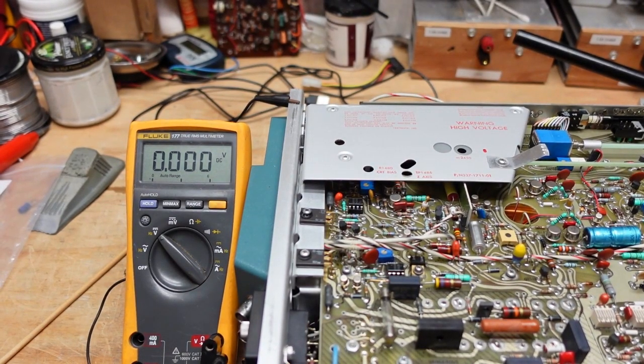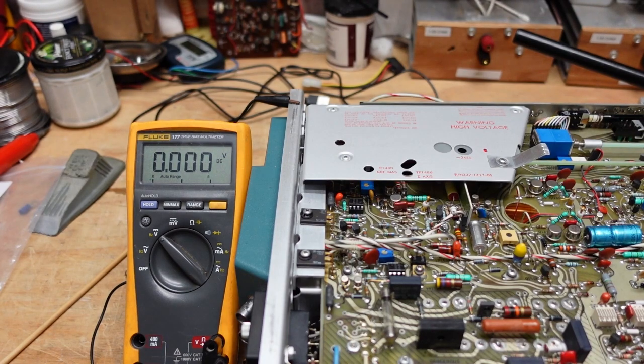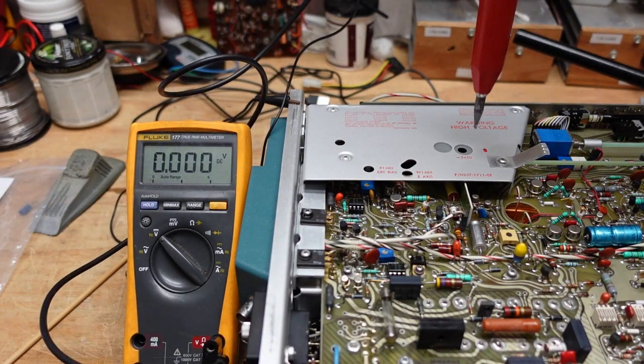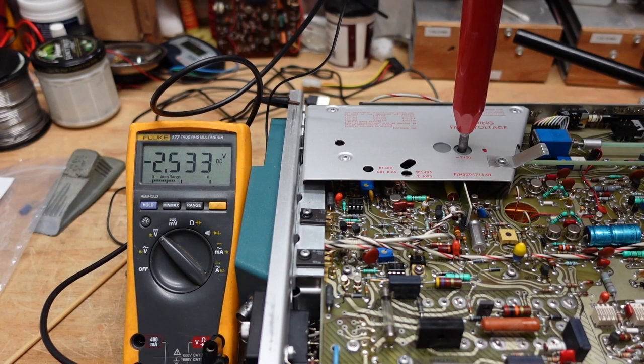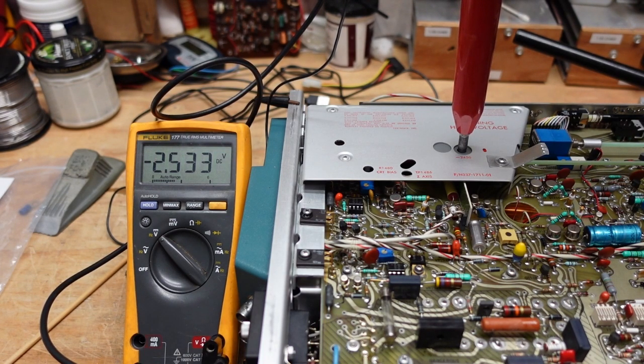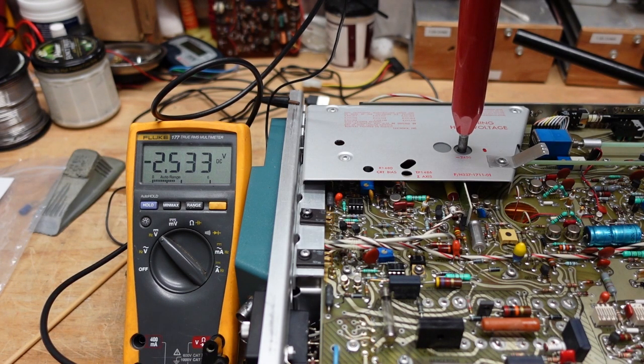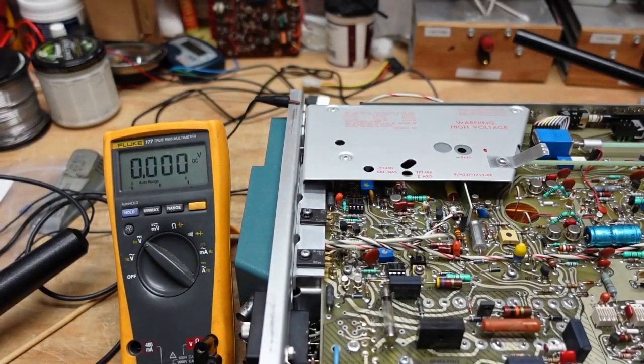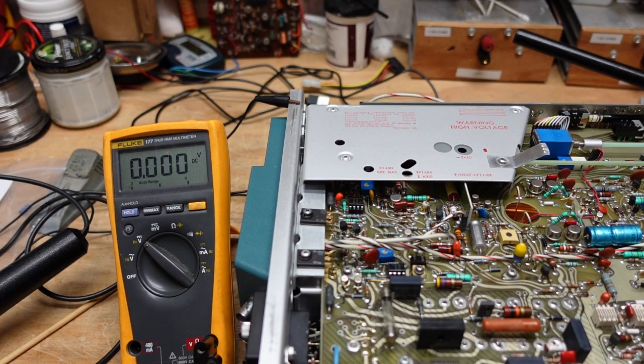We're going to turn this thing on and see what we get. And there you have it: negative 2.533. Now remember this is a thousand to one divider, so that's 2500 volts. It looks like we have good high voltage. However, we need to check the really high voltage, the 14 to 16 kilovolt, and I'll show you how we do that.